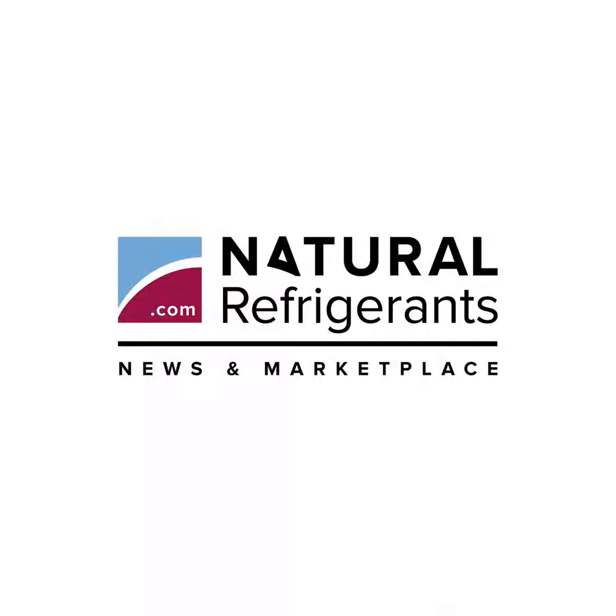6, or 8 cylinders. In June, Frigotec commissioned the largest version of its new R290 chiller with a cooling capacity of more than 400 kilowatts in a jam manufacturing plant, according to authorized Frigotec signatory Lucas Einenkel. Quotable. The project with the Northeim fruit market was a successful start for our Frigonatra series, Einenkel said. Using the IQ module provides detailed compressor and system data, which gives insight into the operating behavior and improves overall system reliability.